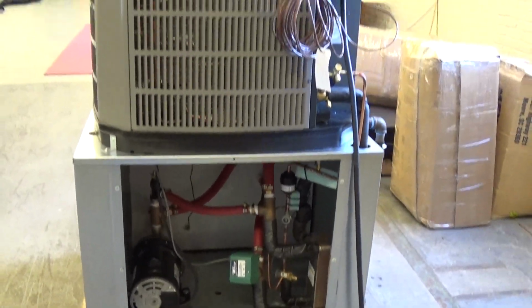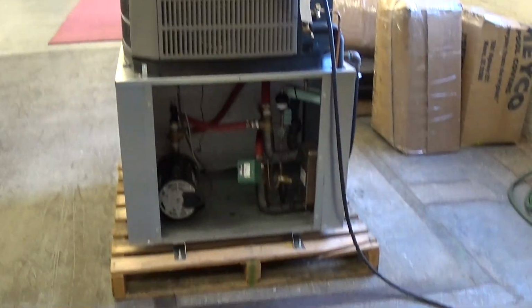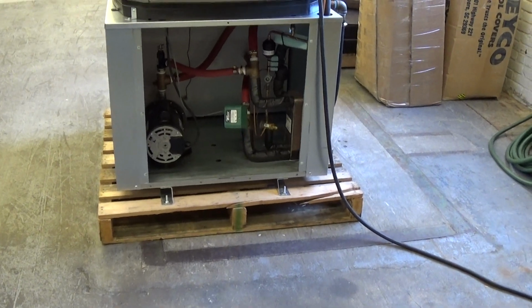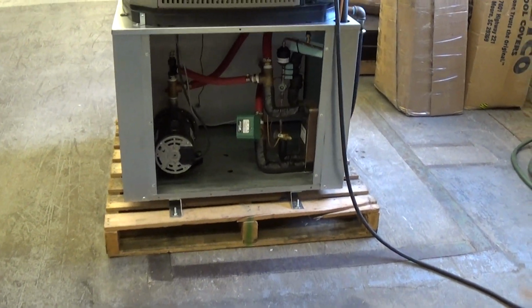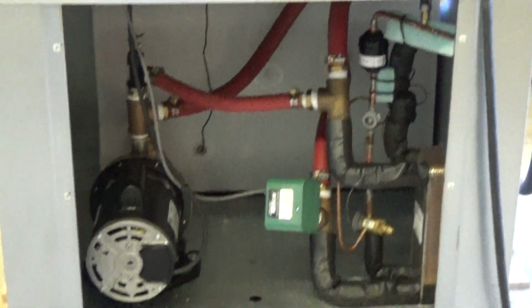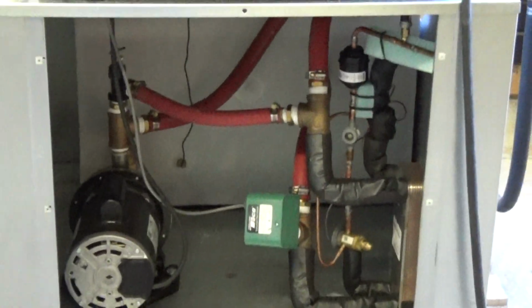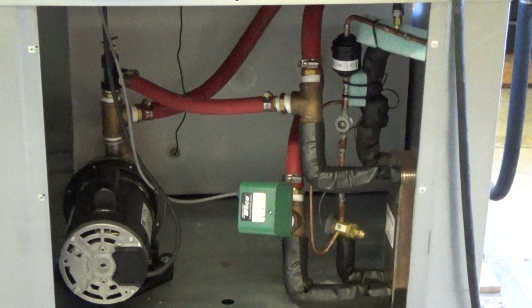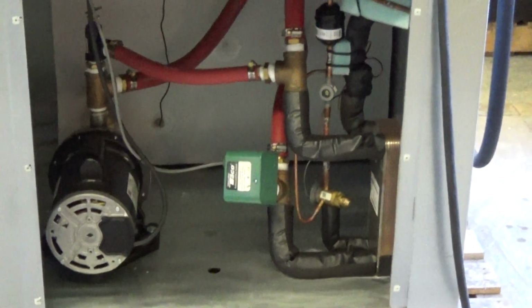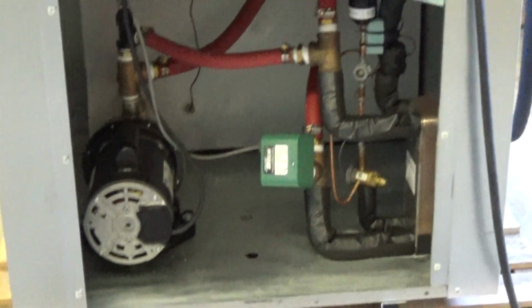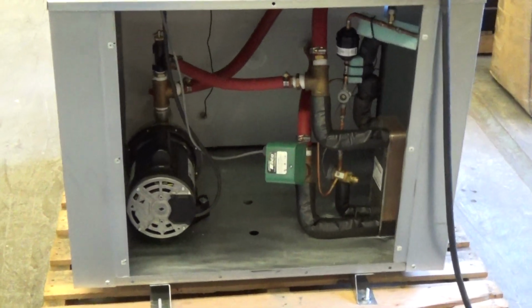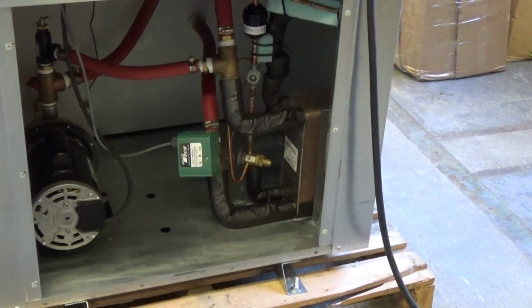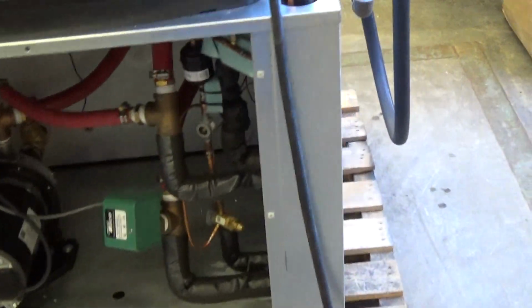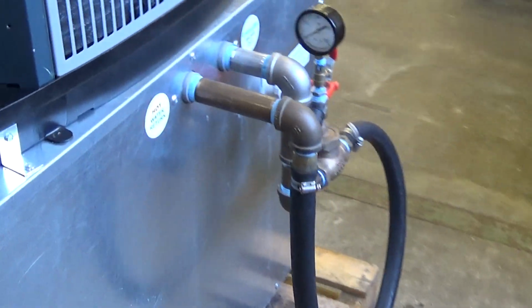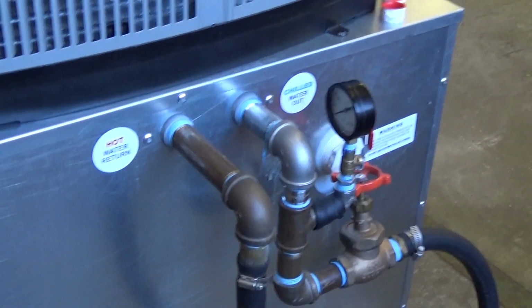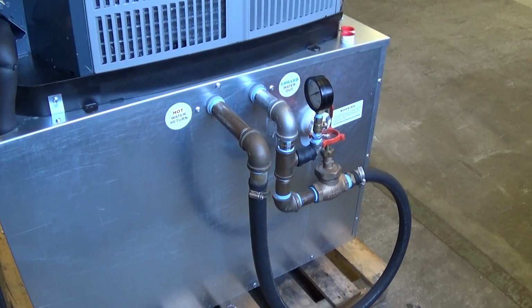However, the same fundamental unit we would use for a brewery 25 Fahrenheit glycol application, in which case you would see all these internal lines insulated, the pump head insulated, and the tank well insulated also. Not to mention, without going into further detail, we would reroute the direction of the piping flow internally, such that the return flow coming back to the chiller would not require any pressure. That's a normal thing that we do if we're repiping something for a jacketed tanks application.